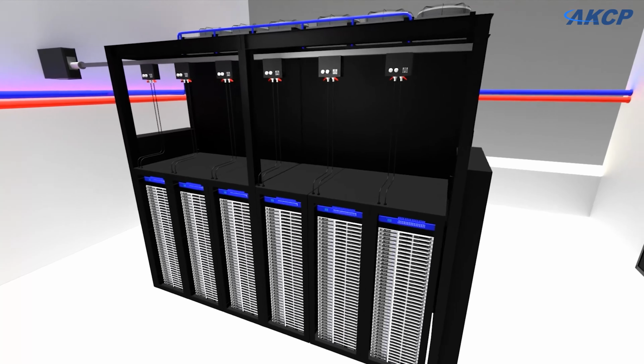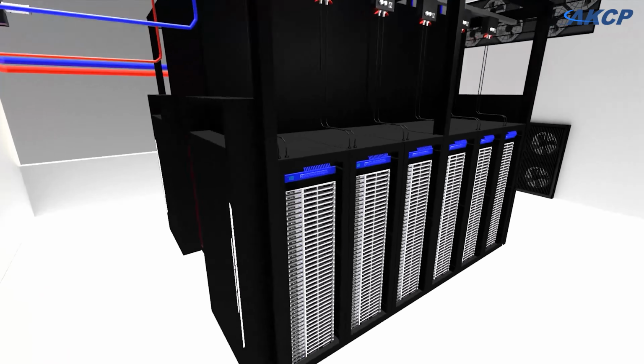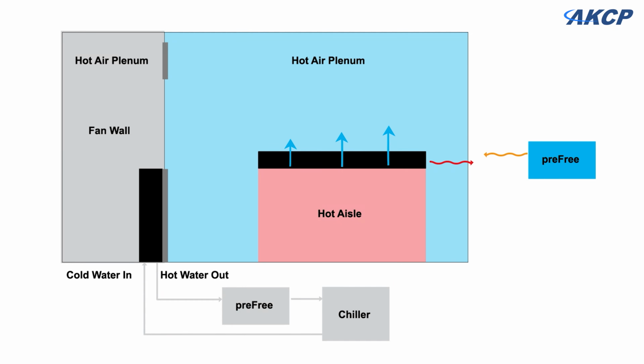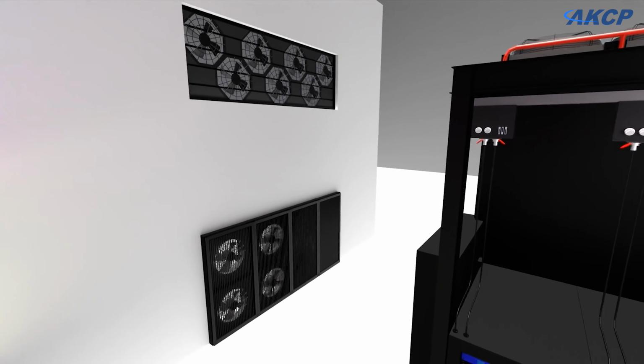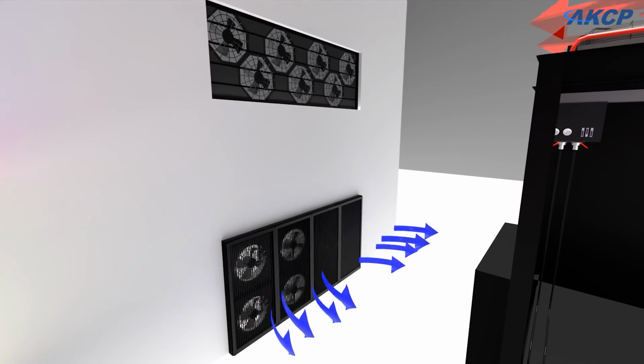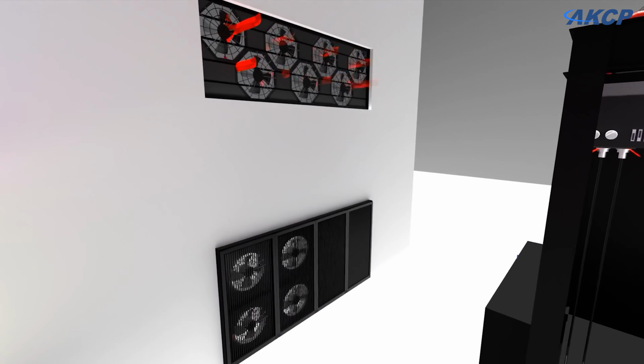These containment rooftop heat exchangers will be pre-cooling, or depending on the outside air temperature, fully cooling the air as it leaves the hot aisle containment. This frees up space so you're not using in-row AHUs, and it also allows it to act as a pre-cooler should you have a fan wall.